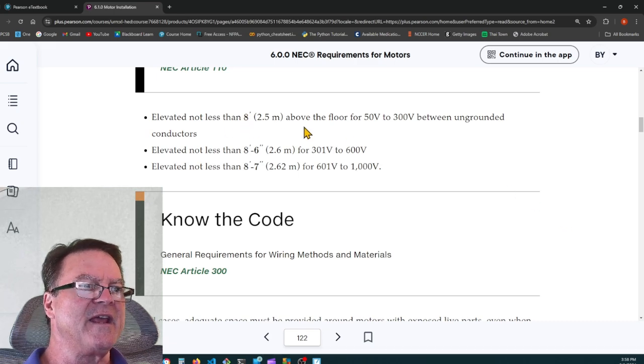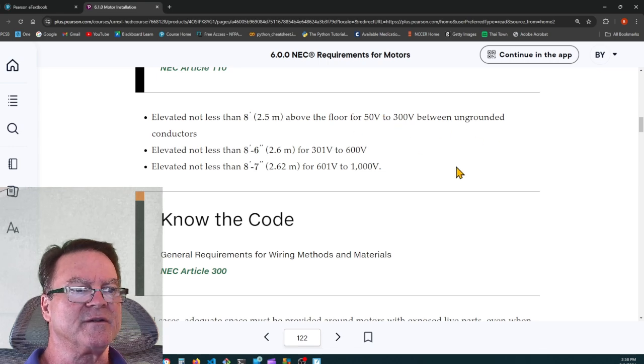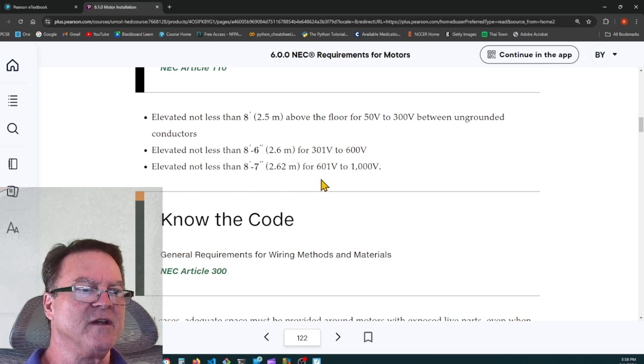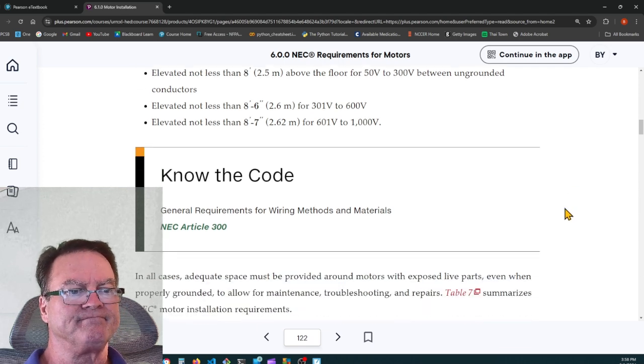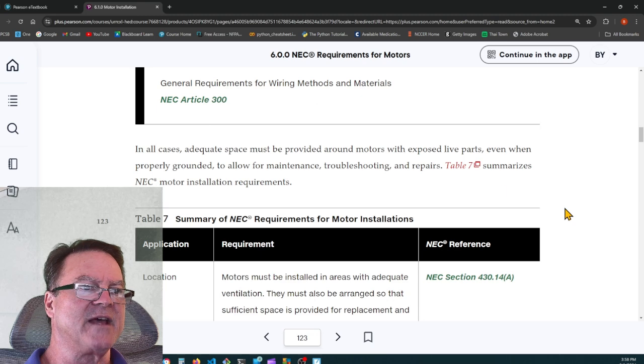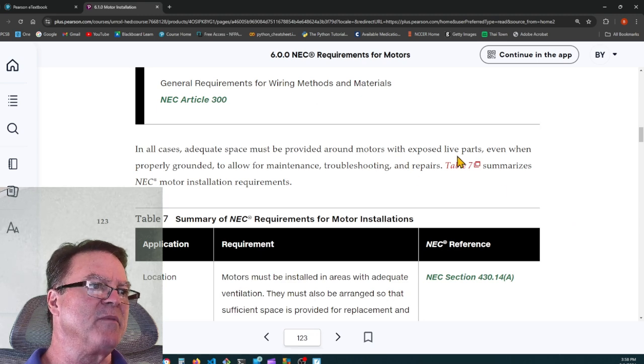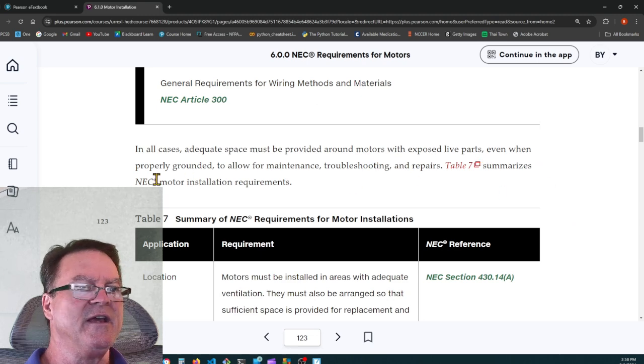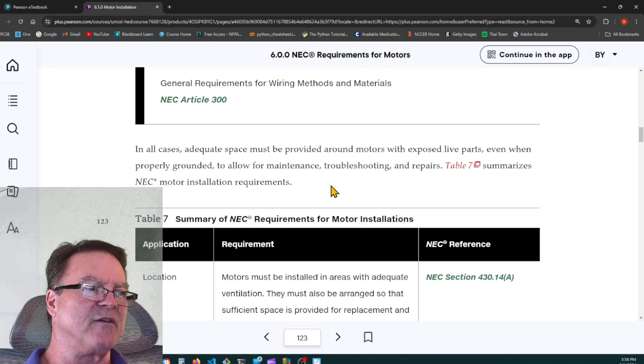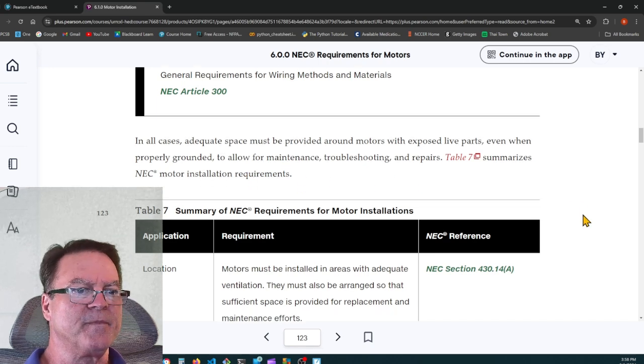Elevated not less than 8 feet above the floor for 50 volts to 300 volts between ungrounded conductors. Elevated not less than 8 feet 6 inches for 301 to 600 volts, and elevated not less than 8 feet 7 inches for motors 601 to 1000 volts. In all cases, adequate space must be provided around motors with exposed live parts, even when properly grounded, to allow for maintenance, troubleshooting, and repairs.